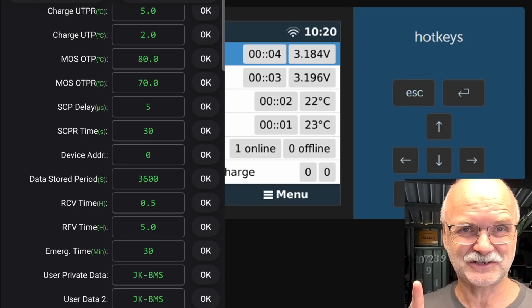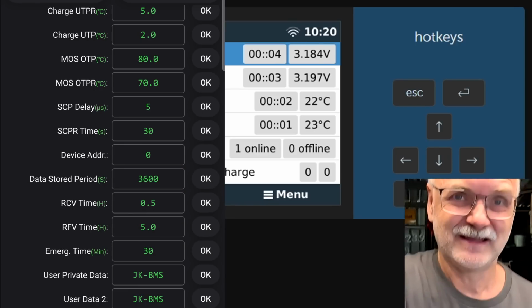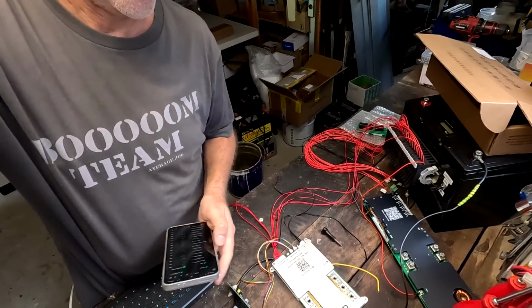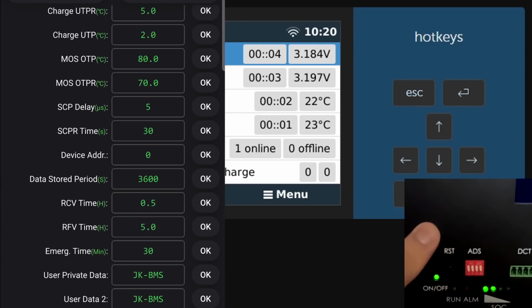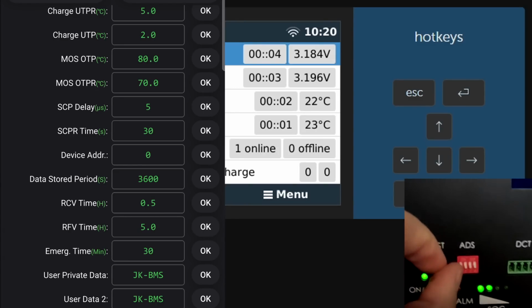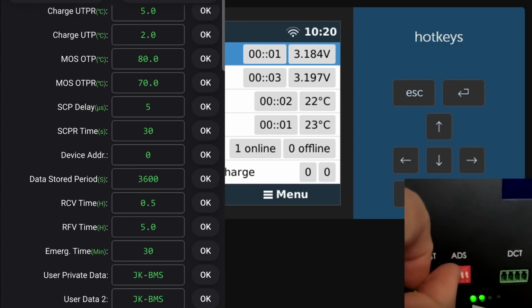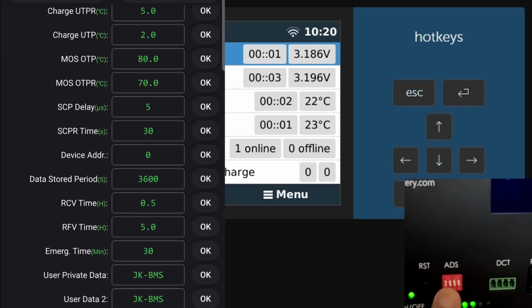Because this is our master. The B-series BMS, this one here on the workbench, is our master. And we want this one here as our slave. So we have to put dip switch number 1 to on, the first slave. Nothing different to what you would do with the inverter BMSs as well.